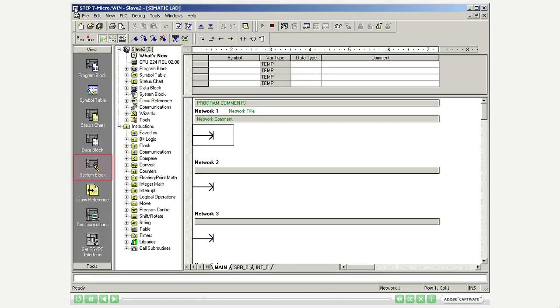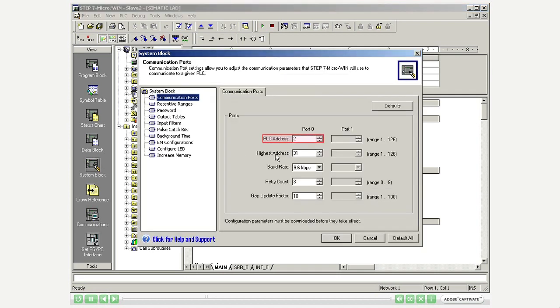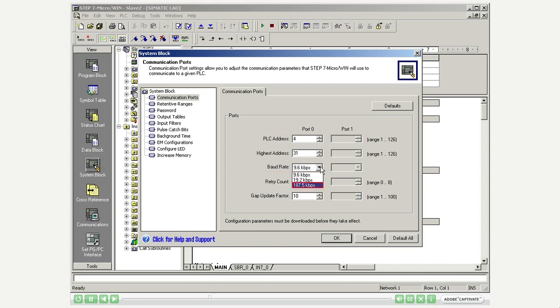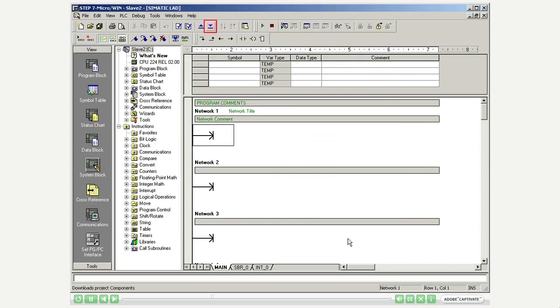In Step 7-Microwin you open the view of the system block. Increase the PLC address to 4. Set the baud rate uniform to 187.5 kilobits per second. Load the settings into the PLC.